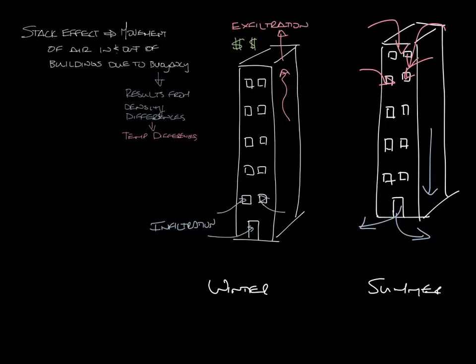Stack effect is one of the reasons that revolving doors were invented. When high-rise buildings were first being built, the stack effect caused so much pressure that the air rushing in was making it hard to open the doors. Stack effect can also cause comfort problems in a building because it may be hard to heat the lower floors due to the cold air being drawn into the building.